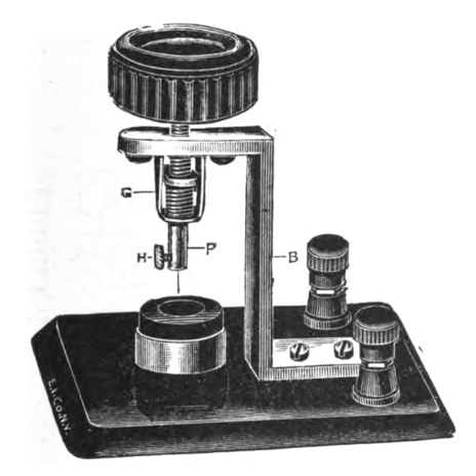The action of this detector is based upon the fact that only the tip of a platinum wire a few thousandths of an inch in diameter is immersed in an electrolyte solution, and a small DC voltage bias is applied to the cell thus formed. Platinum is used because other metals are too quickly dissolved in the acid. The applied bias current decomposes the solution by electrolysis into tiny gas bubbles that cling to the metal point, insulating the metal tip from the solution, thus reducing the bias current.